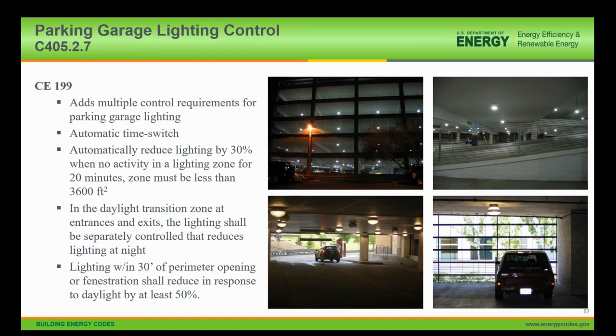The IECC requires the lighting to be reduced by 30% when there is no activity in the lighting zone for 20 minutes, and your control zone is 3,600 square feet. That's consistent with some other energy codes. Again, the upper right image shows a completely empty floor, and yet all the lights are on at full output, which shows why that makes a lot of sense.